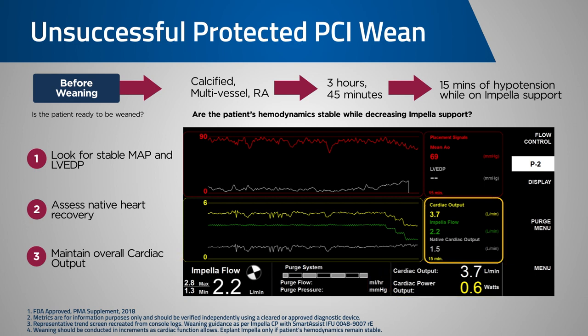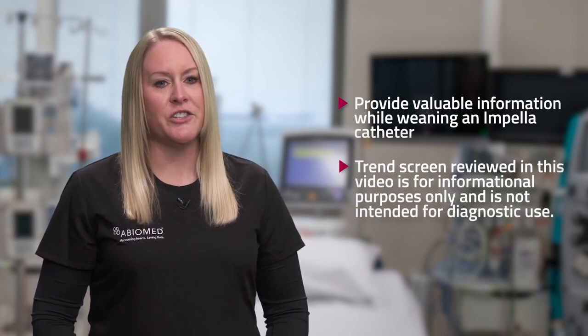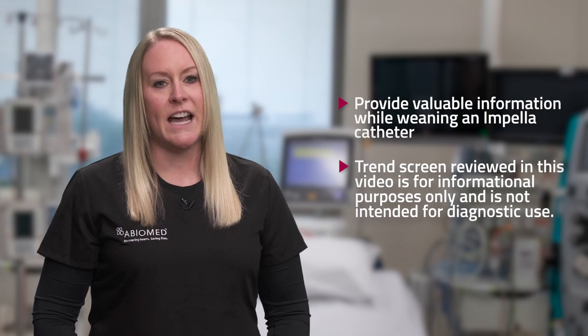These trends observed here may be indicators that this patient is not ready to be weaned off Impella support. In summary, the trend screen provided with the Smart Assist technology can provide valuable information while weaning an Impella catheter. Remember, the trend screen reviewed in this video is for informational purposes only and is not intended for diagnostic use. Patient hemodynamics should be verified using approved diagnostic devices. If you have any further questions, please contact your local Abiomed team or the Clinical Support Center.